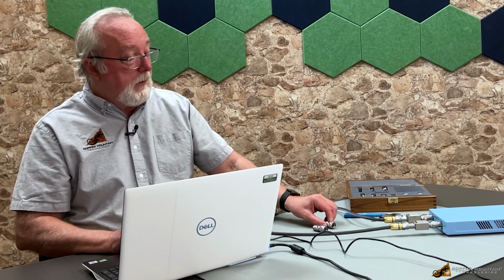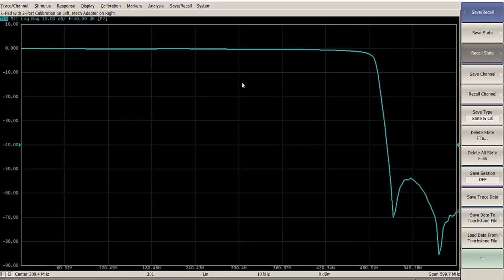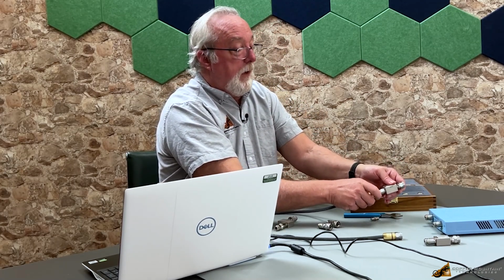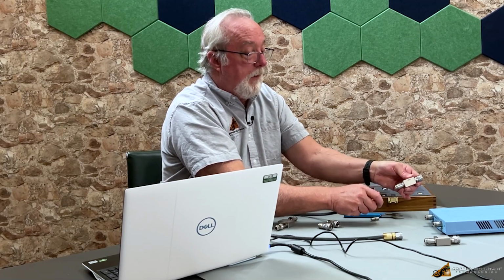I also connected the mechanical adapters and performed calibration once again and measured the same filter. I did this in another channel, which I have set the trigger to hold, so I can compare the two measurements. So let's do that. I will do the calibration with mechanical adapters instead of the LPADs. I should mention that the LPADs, while they do provide a good broadband 75 ohm match, have about 7.5 dB loss each side. So you will lose 15 dB of dynamic range if you are using these, whereas the mechanical converters have essentially no loss.